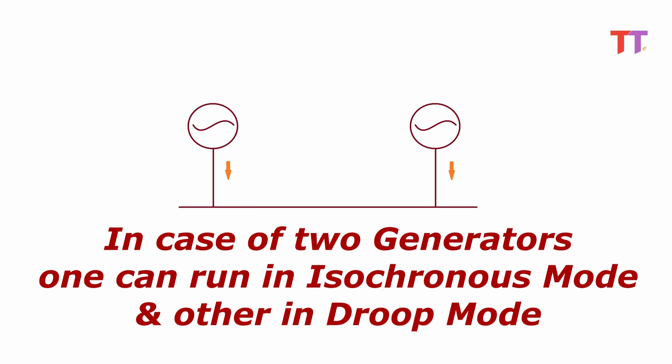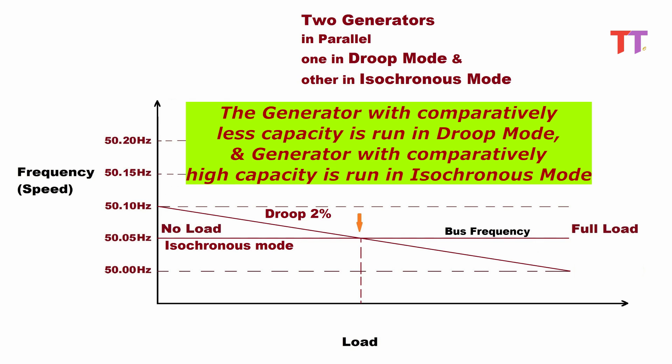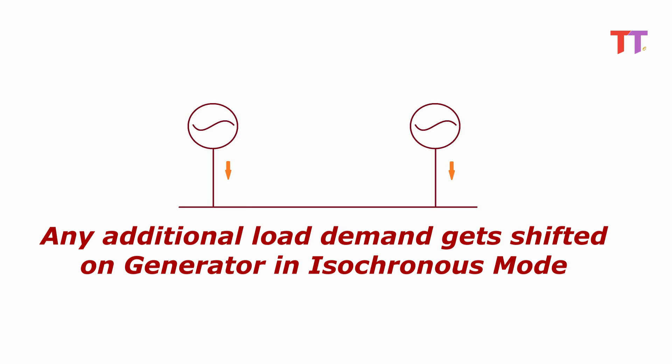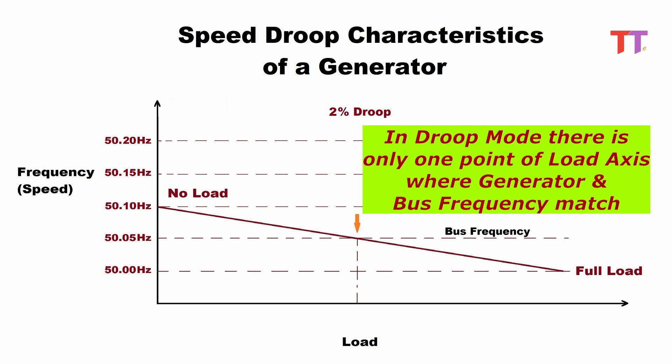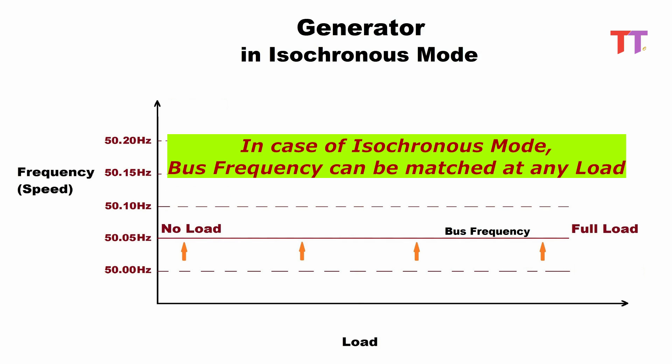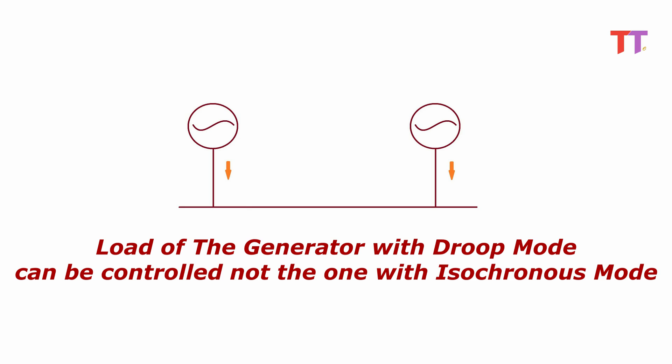In case of two generators, one can run in isochronous mode and the other in droop mode. The generator with comparatively less capacity is run in droop mode, and the generator with comparatively high capacity is run in isochronous mode, because any additional load demand gets shifted onto the generator in isochronous mode. Here in the graph we can see that in droop mode there is only one point on the load axis where generator and bus frequency match, whereas in isochronous mode, bus frequency can be matched at any load. Hence the load of the generator with droop mode can be controlled, not the one with isochronous mode.